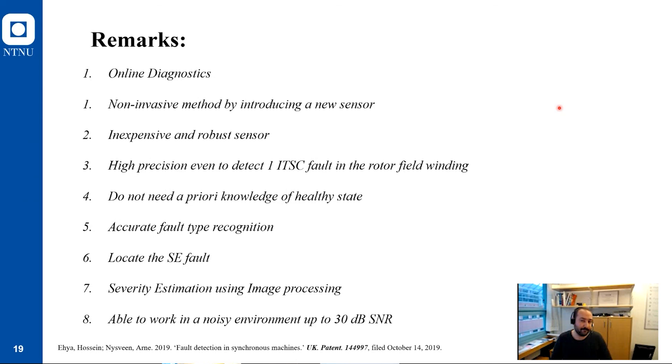The remarks of the project: the method is able to detect the fault online. It's non-invasive, so we don't need to stop the machine. The sensor that we developed is inexpensive and robust. It has really high accuracy. We can detect the fault in its earliest stage. For instance, one interturn short circuit fault or 10% static or dynamic eccentricity. The most important thing is we don't need prior knowledge of healthy machine. The generators are working for decades, so it's impossible to have data from a healthy machine. With this method, we don't need it. The method is also able to determine a fault. In this way, we can reduce maintenance time because we know which part is faulty.